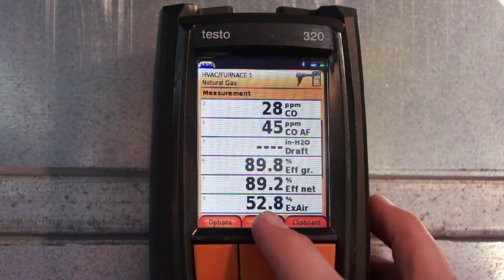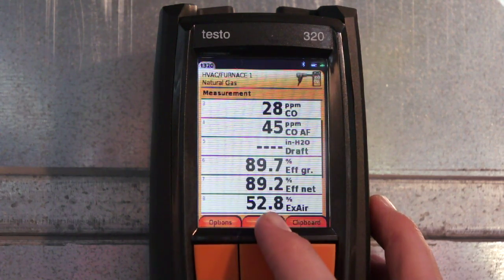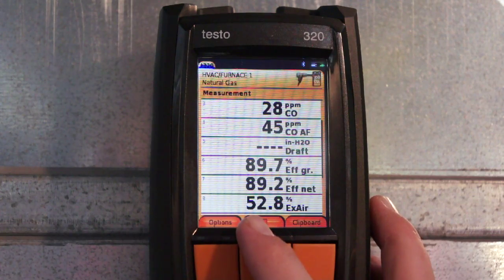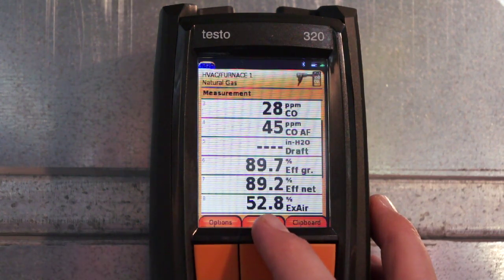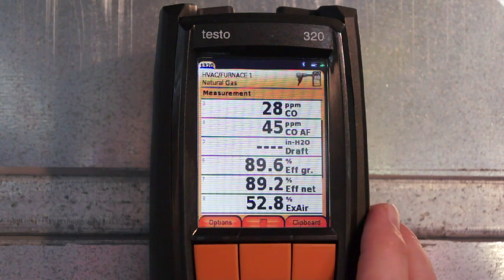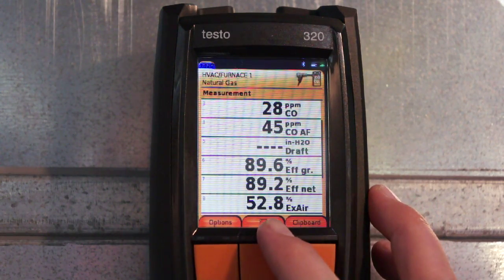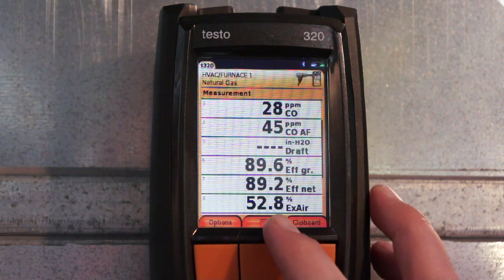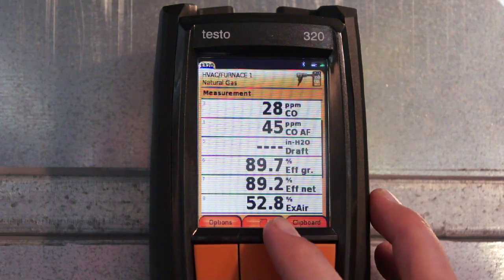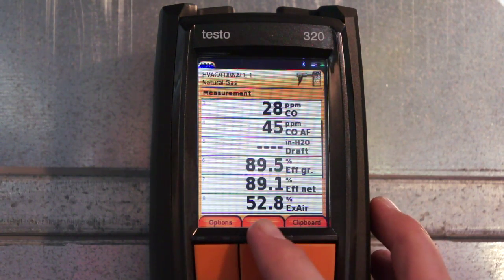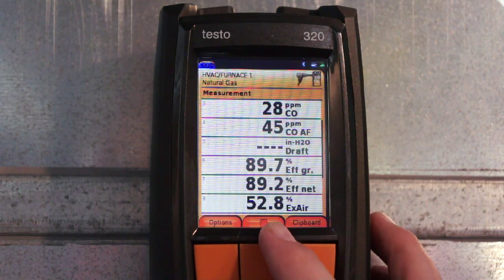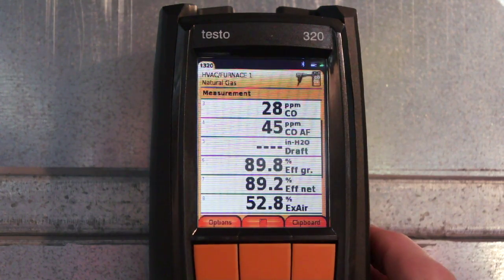If I scroll down again here, on line 8, I have excess air. This appliance I want to see run with about 50% excess air. That gives me enough excess air to assure safe combustion for a residential appliance. That could run as low as 30% on a 95% efficient furnace because they don't want the excess air to dilute the flue gases and lower the dew point temperature of the flue gas. But in this case, 50% is exactly what I want to see. I'm real happy with that number right there.